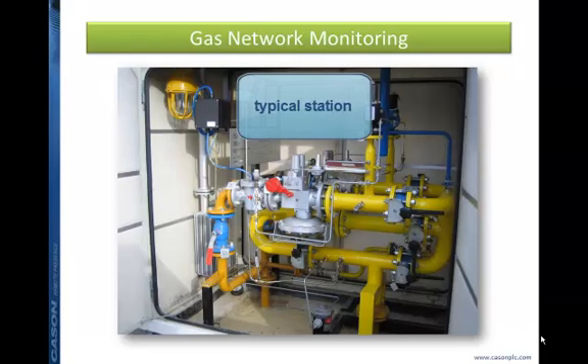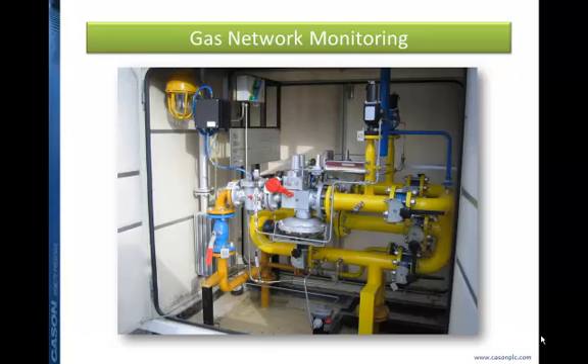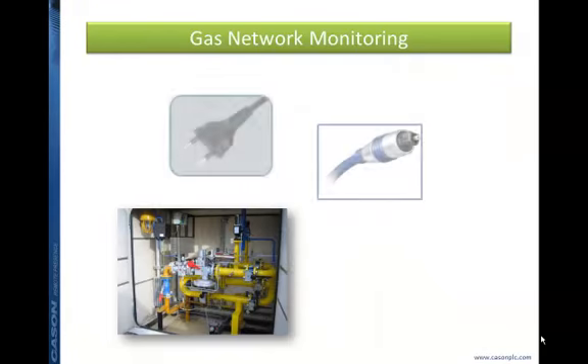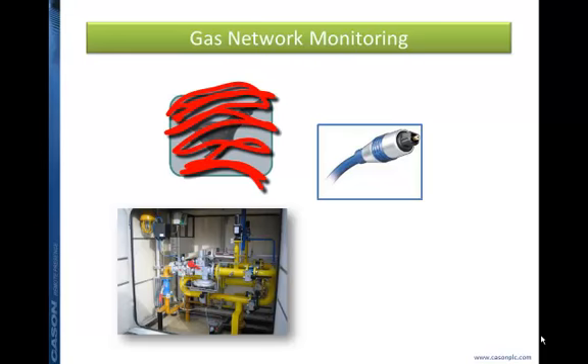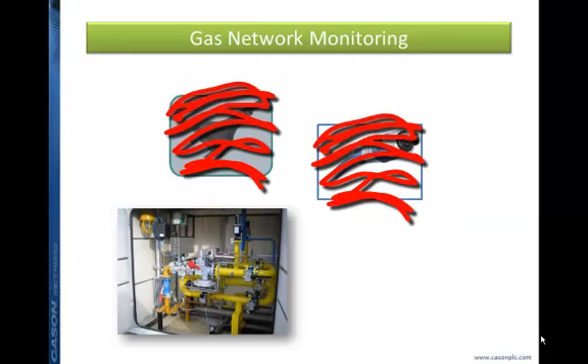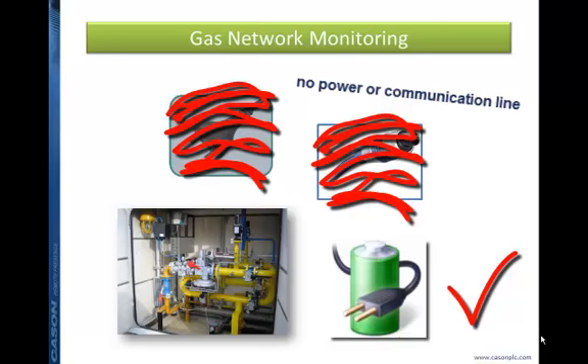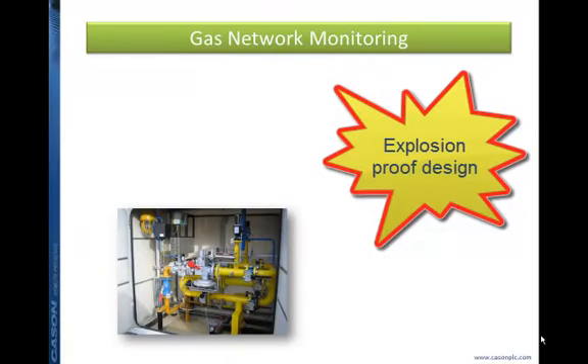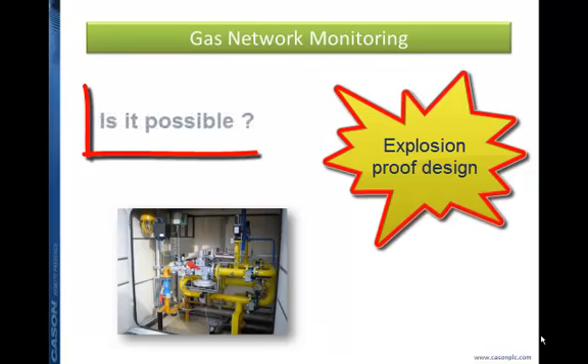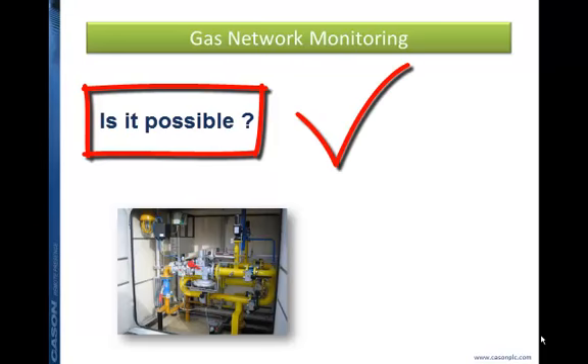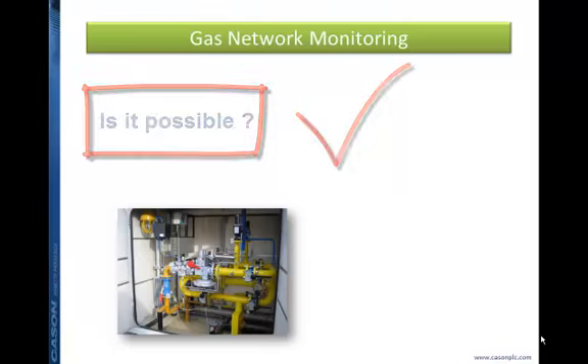Now we can see a typical gas pressure regulating station, a cabinet plant type. You can see similar facilities all over the world. Probably you cannot see power or communication cables on the field. Yes, this is the biggest challenge because all the installed electronic devices have to be operated by batteries, and to make the situation even more difficult, the cabinet and the place around it is an explosion hazardous area. So you can install devices with only explosion-proof design. You can say it is impossible, but I can show you how easy it is to do.